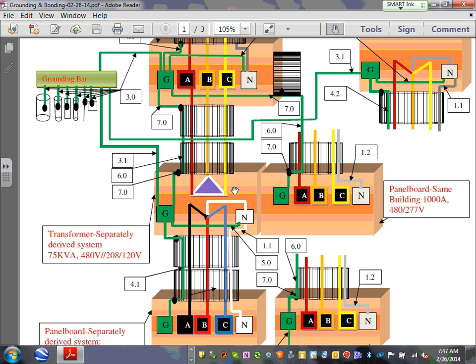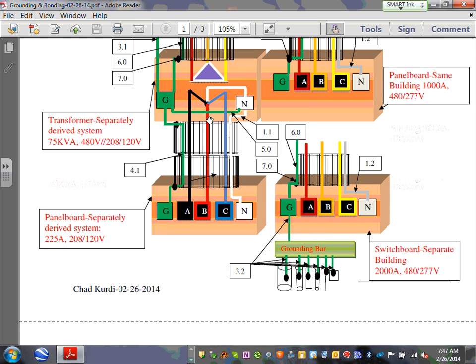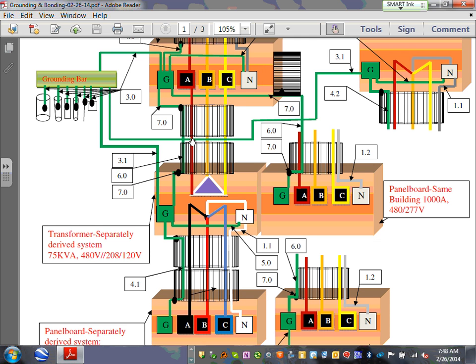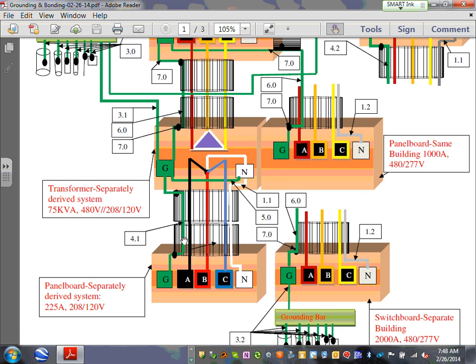Can you guys see that? To a transformer. This is a delta-Y transformer, 75 kVA, 480/120. That's called a separately derived system transformer. This is the receptacle transformer, Adam, the one that we did in math, the receptacle transformer that we're supposed to do for our receptacle panel. Then we took a feeder from this transformer directly into a 225 amp, 120 receptacle panel.